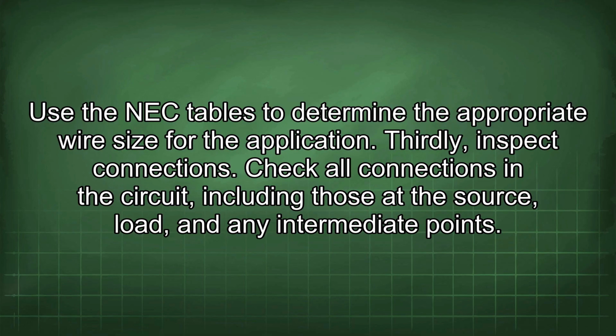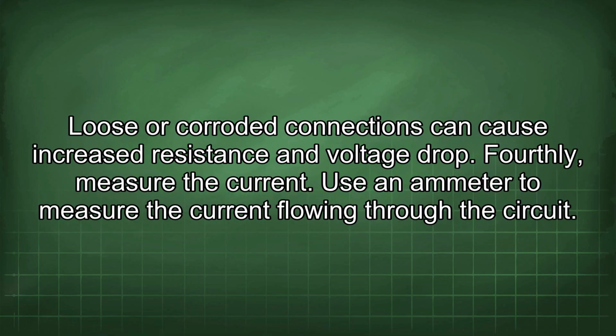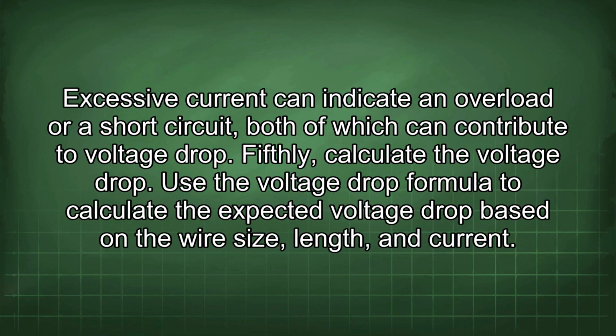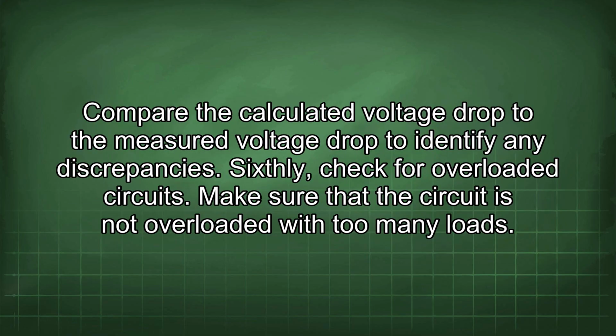Thirdly, inspect connections. Check all connections in the circuit, including those at the source, load, and any intermediate points. Loose or corroded connections can cause increased resistance and voltage drop. Fourthly, measure the current. Use an ammeter to measure the current flowing through the circuit. Excessive current can indicate an overload or a short circuit, both of which can contribute to voltage drop. Fifthly, calculate the voltage drop. Use the voltage drop formula to calculate the expected voltage drop based on the wire size, length, and current. Compare the calculated voltage drop to the measured voltage drop to identify any discrepancies.